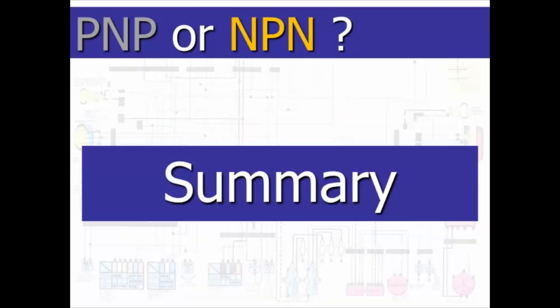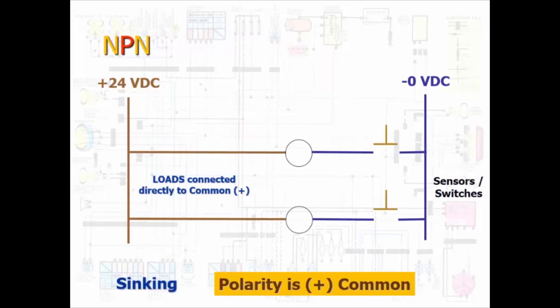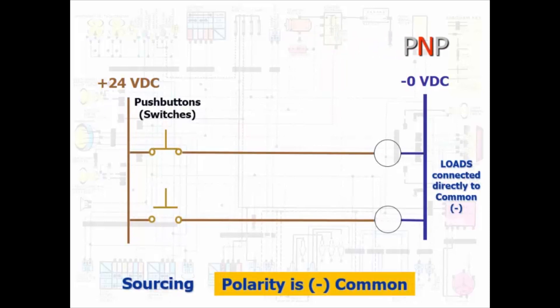So, for resolving NPN or PNP circuits, remember this. NPN has the loads directly connected to the positive common. The voltage must go through closed switches to sink from 24 to 0 volts. But PNP circuit loads are directly connected to the negative common. Voltage must go through the closed switches from the source to the negative common.